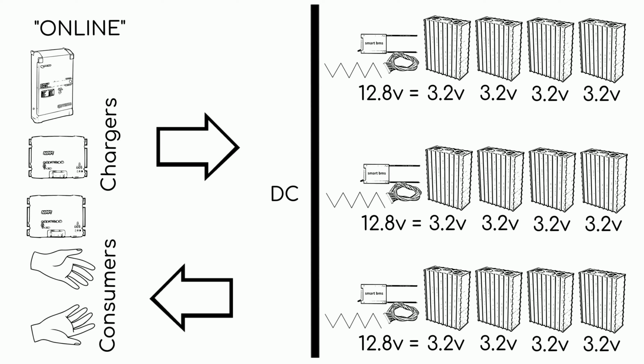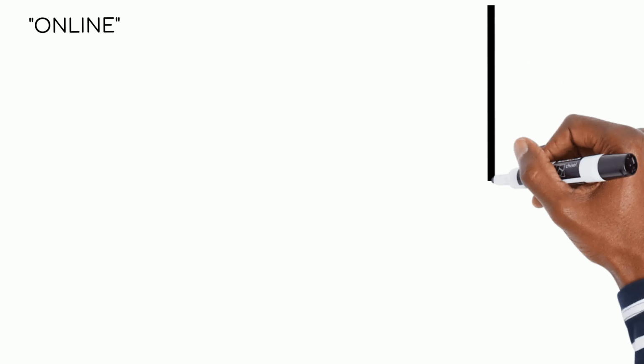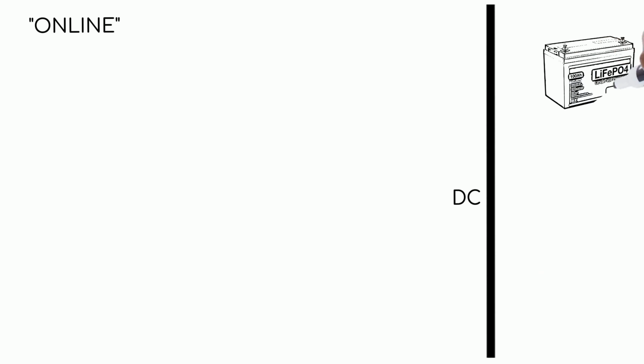Synchronization of chargers using BMS is impossible due to the lack of centralization. With proper system design, it can only be done in a passive way, using cables of equal cross-section and length. Some equipment manufacturers offer the option of synchronizing chargers by combining them into a network, together with vSense devices.